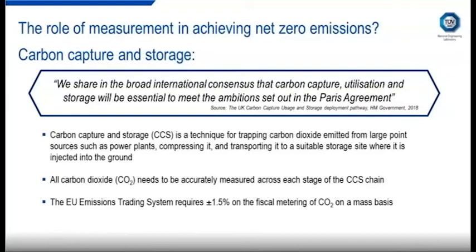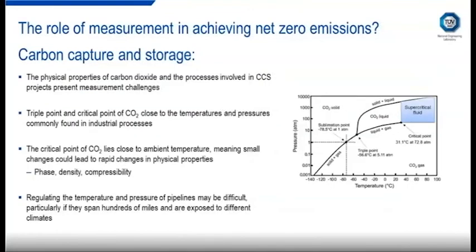Now, in terms of the actual accuracy requirements, the EU emissions trading scheme requires an accuracy of 1.5% on the overall mass of CO2, whether it's derived from flow rate measurements or otherwise. This could be very challenging because carbon dioxide has fluid properties that can be very difficult to work with, depending on your operating conditions. The challenge is that the critical point and the triple point occur at pressures and temperatures which are quite close to typical operating conditions. So the critical point especially occurs at 31 degrees C. What this means is that small changes in temperature could result in quite large changes in fluid properties, and you're always quite close to the phase boundary for many applications. So it has implications for the phase of the fluids. There could be a phase change, or there could be changes to fluid properties, including density.